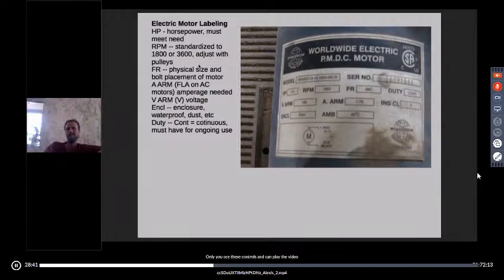DC motors have what's called A-arm, which is amperage on the DC motor. On AC motors that's generally labeled FLA, full load amperage, which tells you how many amps you need. V-arm is usually voltage on a DC motor, telling you the voltage needed. Again, you're aiming for the same ballpark as what you can produce from your solar system or whatever.